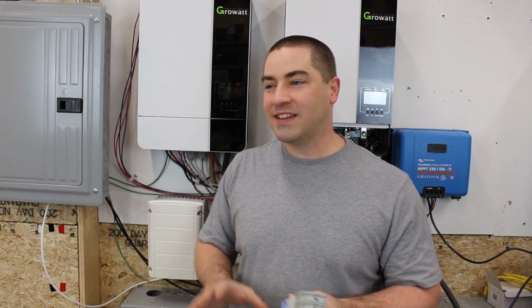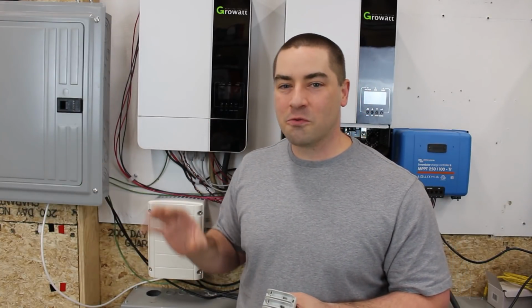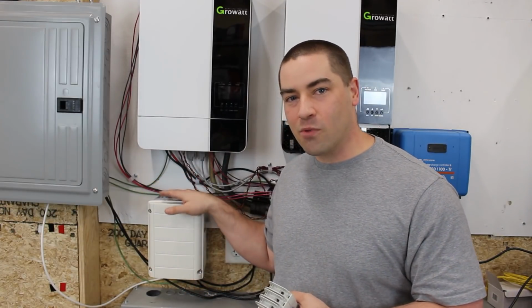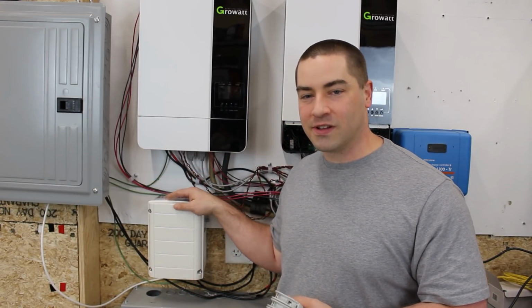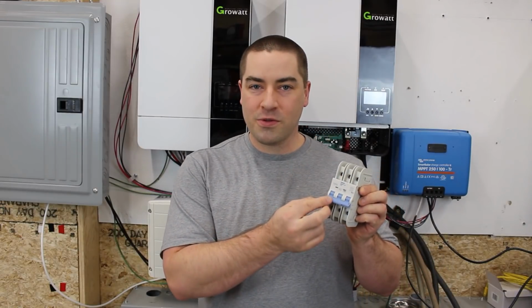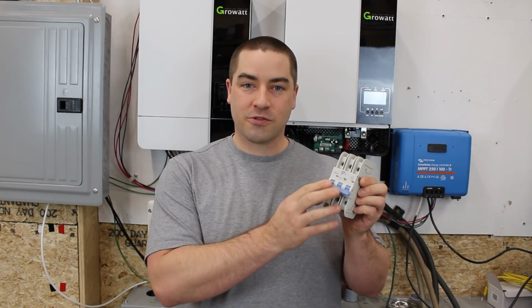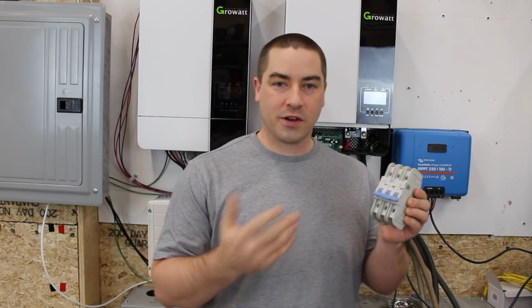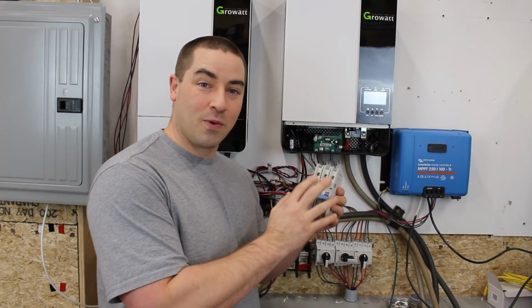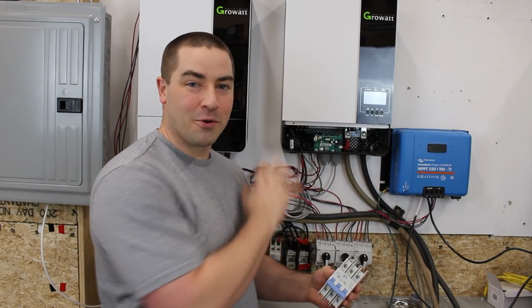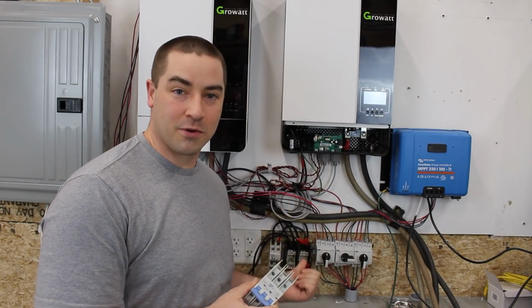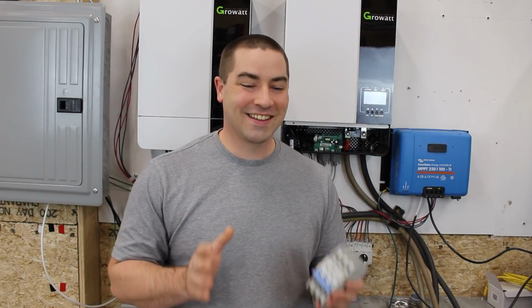But if I completely loaded one phase without any load on the other, I'd have more than 32 amps on the neutral. It'd be going through this, and eventually it would trip this circuit breaker according to the trip curve. When it did that, it would kill both inverters from powering the terminal block. So I think this is a winner.